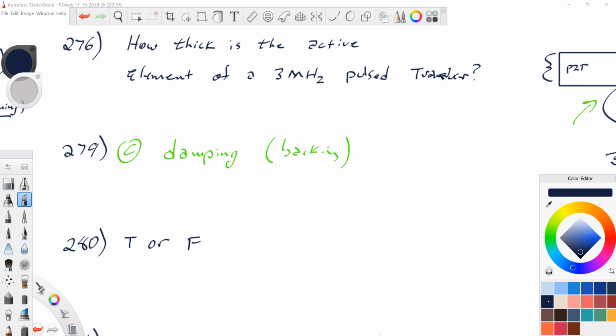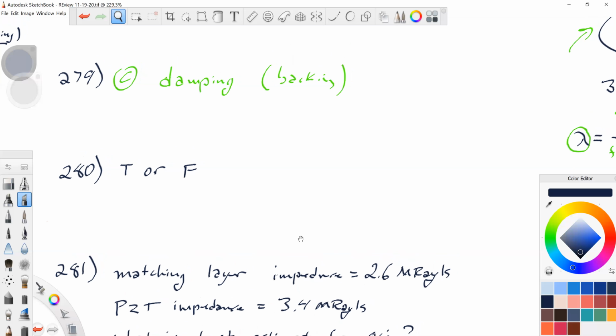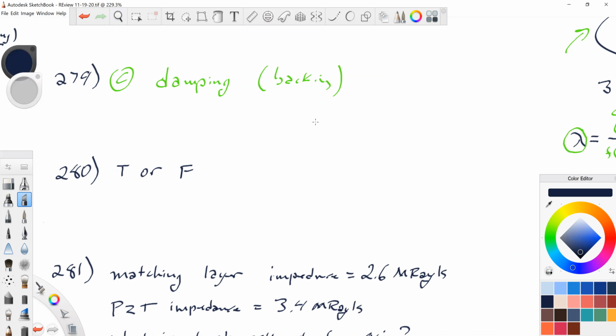Okay, 280, true or false? The characteristic impedance of acoustic gel is greater than the matching layer's impedance, but less than the piezoelectric element's impedance. Okay, let's break this down and think about this without just jumping right into a true or false. Well, the answer is false, so I just jumped in. But why is it false? Okay, so gel is greater than matching layer impedance, but less than piezoelectric.